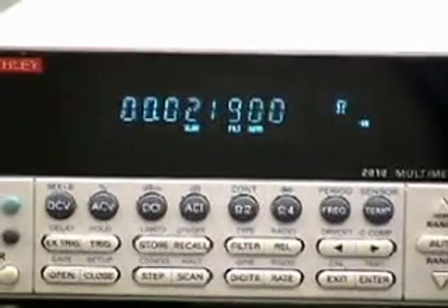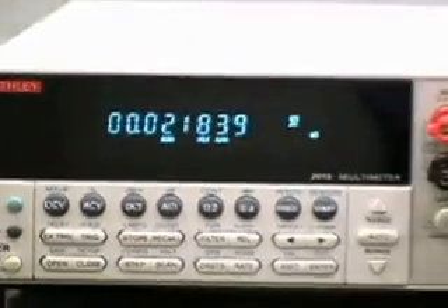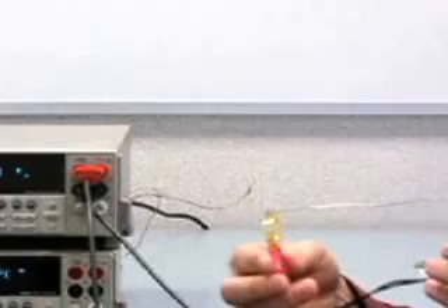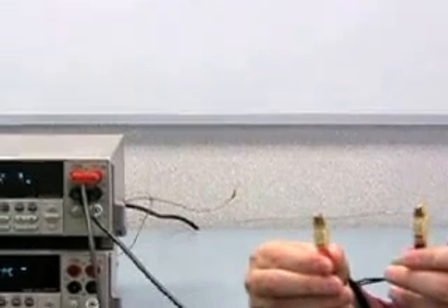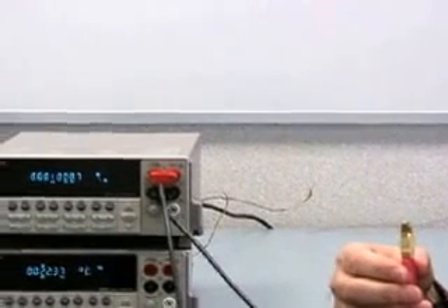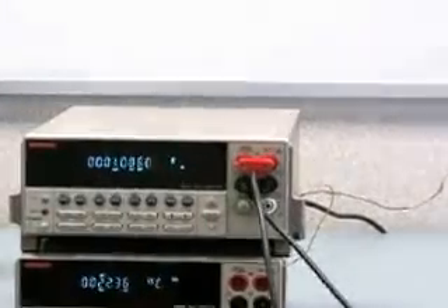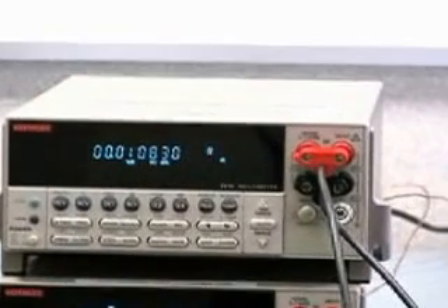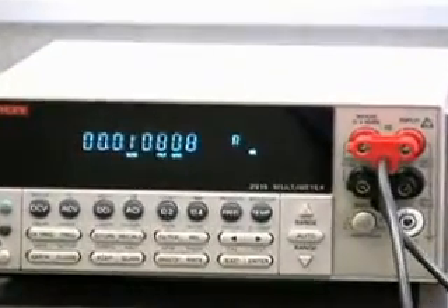Okay, it's about 22 milliohms. How can I know if that's real? If I were to move the clips halfway in, we should see about 10. Watch that. About 10.8. So I know this is operating properly. Okay, so this is really good for this.